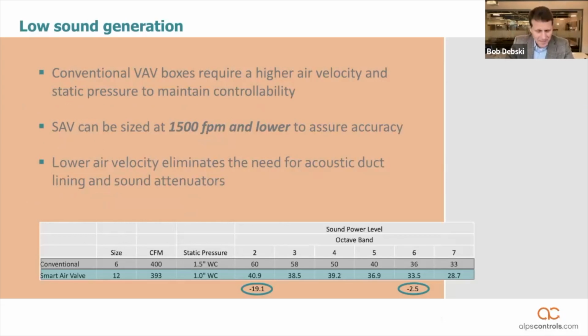Low sound generation. We talked about this. We reduced the airflow velocity, we reduced the noise. And because of the reduction in airflow velocity, comparing that to a conventional VAV box, in the lower octave bands of sound generation, you can see a 20 dB decrease with the smart air valve. A 20 dB decrease is equivalent to 100 times less sound generation. So what does that mean? It means you get to eliminate the internal acoustic insulation as well as any sound attenuators. Get rid of any internal insulation. You eliminate that potential issue of fibers being transmitted into the space. And when you eliminate the sound attenuators, you not only eliminate cost, you also simplify the design significantly.